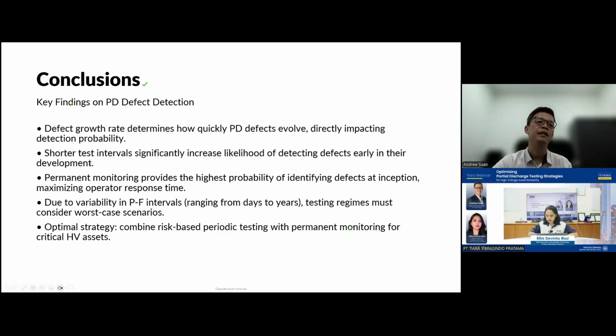Last but not least, your optimum strategy. What's the best strategy? Combine your risk appetite with periodic testing. If you cannot afford failure - because failure can cost your factory, chemical plant, or oil and gas rig millions of dollars within a few hours - then you may want to consider investing in a permanent monitoring system, because it will be the first to save you, since it detects PD.